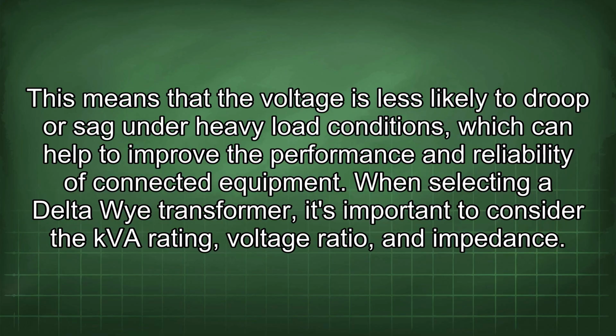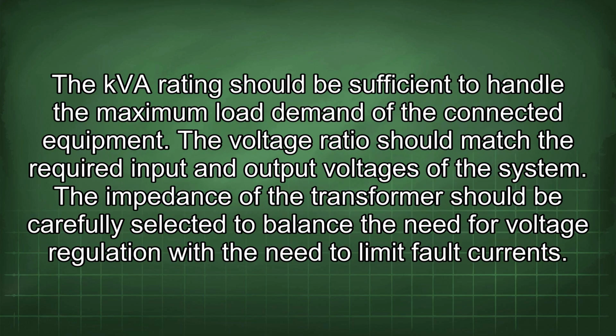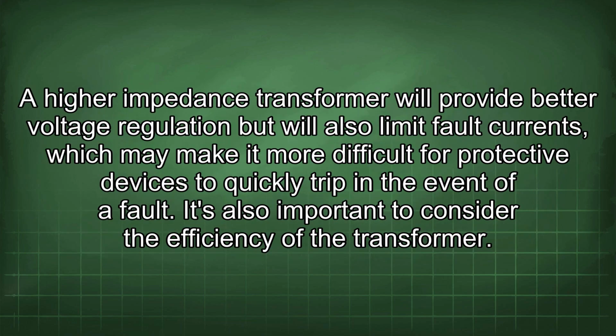When selecting a Delta Wye transformer, it's important to consider the kVA rating, voltage ratio, and impedance. The kVA rating should be sufficient to handle the maximum load demand of the connected equipment. The voltage ratio should match the required input and output voltages of the system. The impedance of the transformer should be carefully selected to balance the need for voltage regulation with the need to limit fault currents. A higher impedance transformer will provide better voltage regulation but will also limit fault currents, which may make it more difficult for protective devices to quickly trip in the event of a fault.